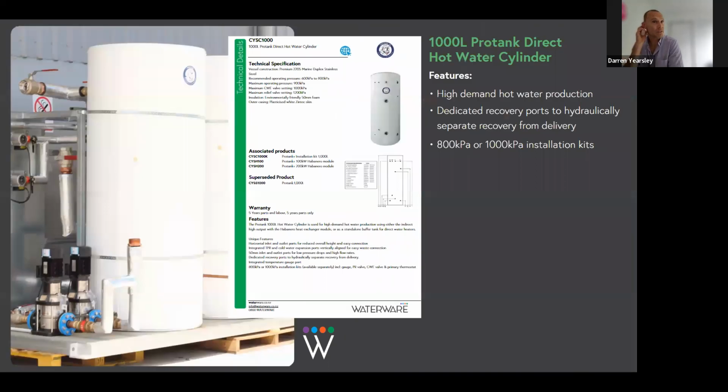And then for the storage cylinders, we have two platforms, either 500 litre or 1,000 litres. Again, we run them in an array. So if we need 3,000 litres of storage, we'd have three 1,000 litre tanks. We'd always run a minimum of 2 cylinders, so we have some sort of redundancy built in, but typically you find you have more than 2.